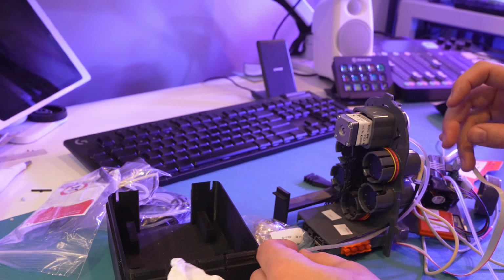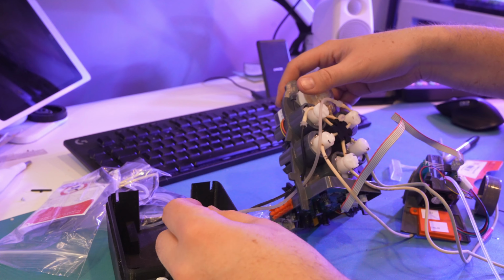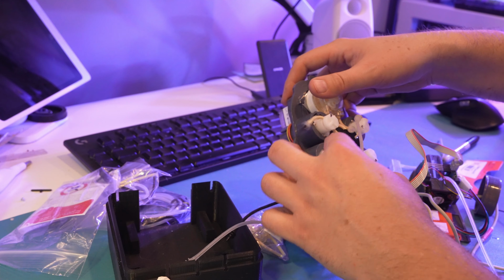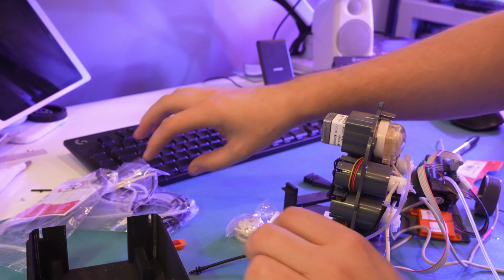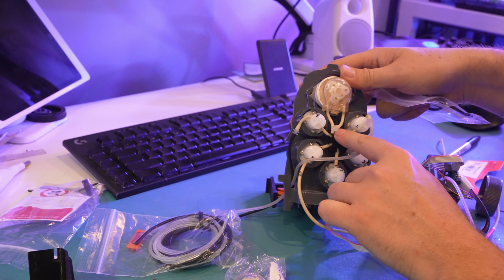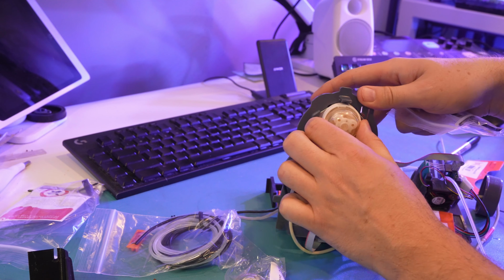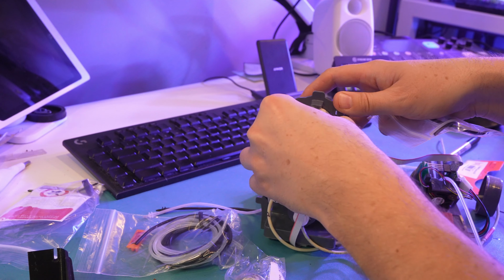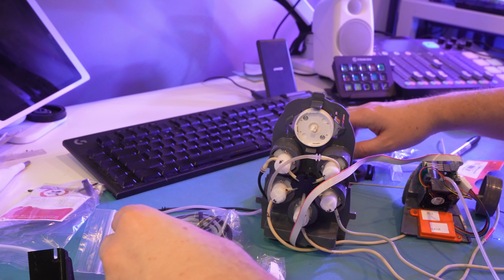So next on the list, I am going to replace these internal lines for our sample and our waste. Okay, so our pump head goes to the 12 o'clock position. So I'm going to unhook that, take off the old pump head, and we will install the new one.